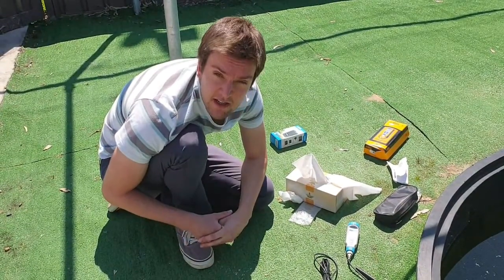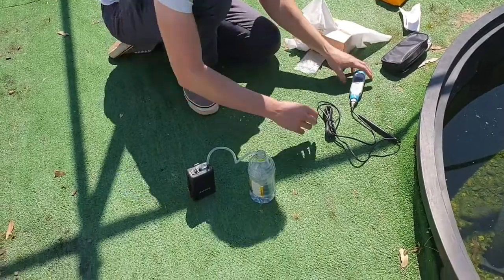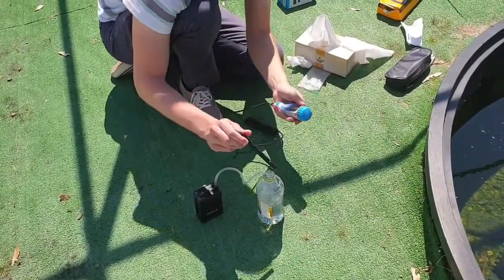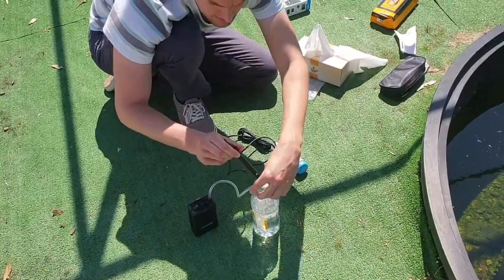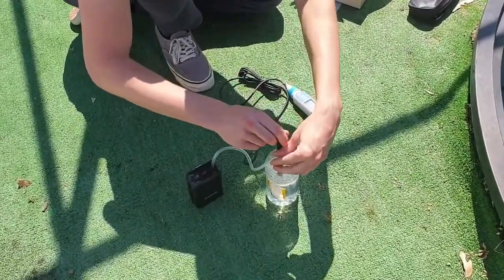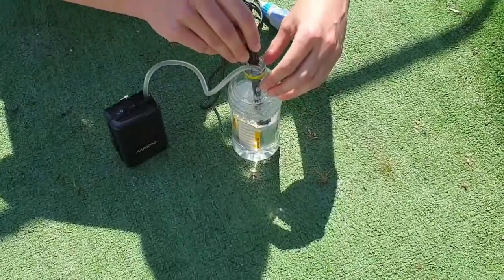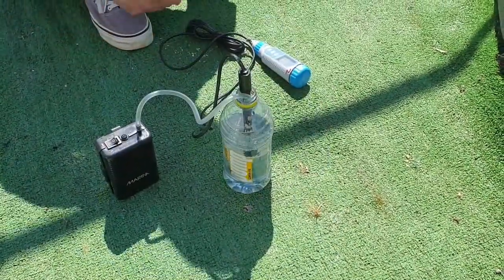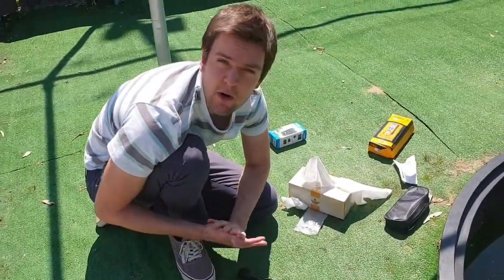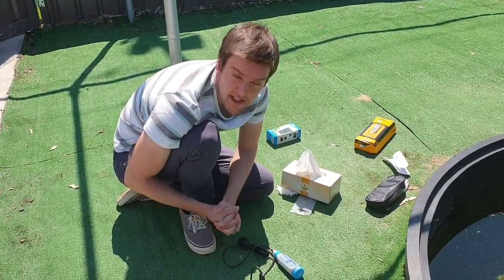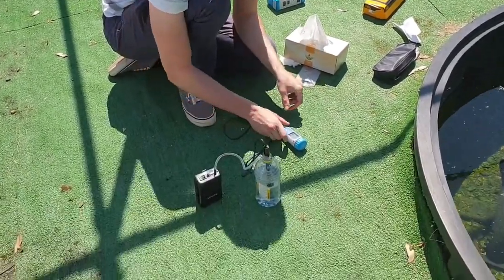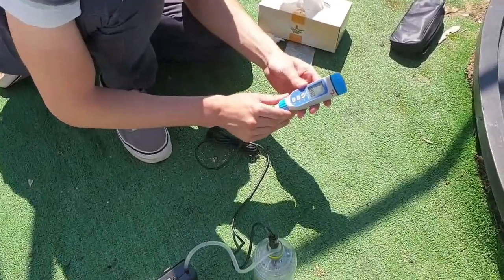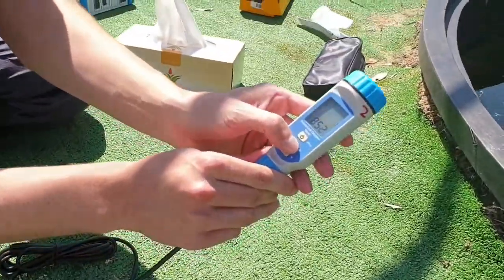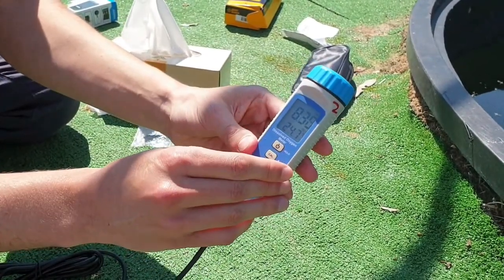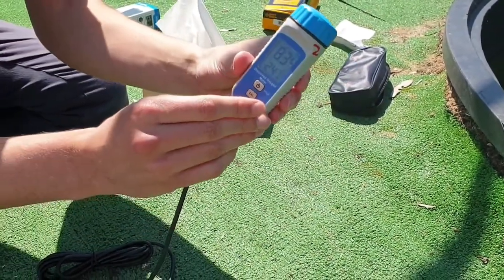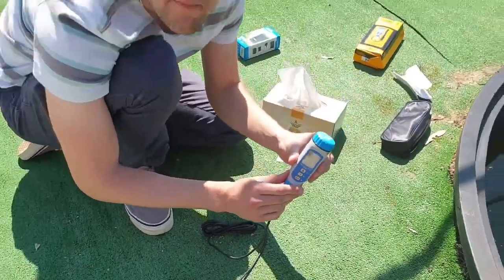So the water's been bubbling for approximately a minute now. So now we immerse the probe into the bubbling water, and we simply leave the probe immersed in the water for about 30 seconds before calibrating the 1 point. So the probe's been immersed in the bubbling water for about 30 seconds now. So now we can calibrate the 1 point. So again, just like the 0 point, we press cal, and you can see the PASS message came up. So now the probe is calibrated and ready to be used.